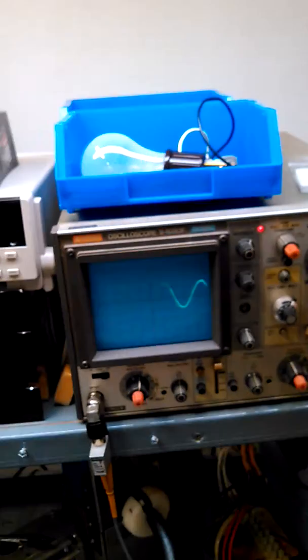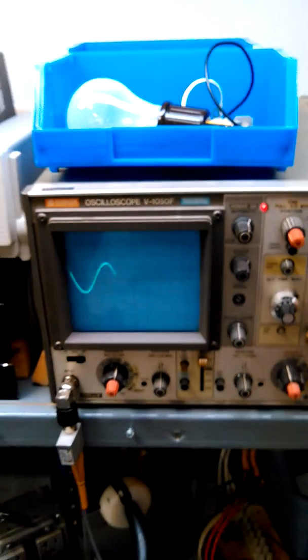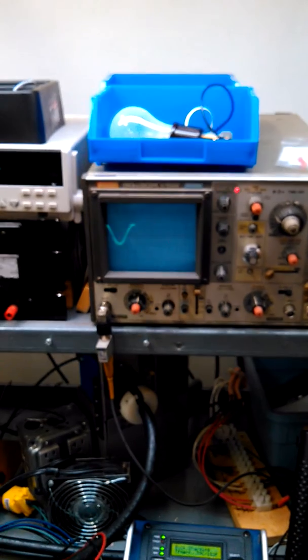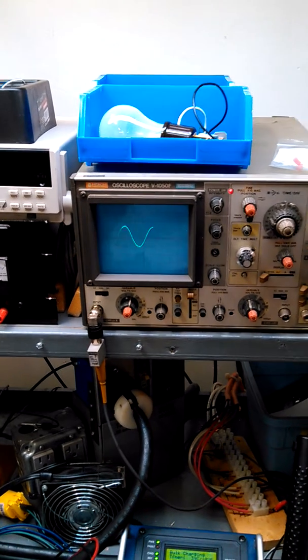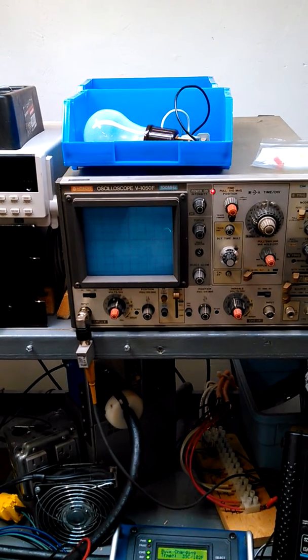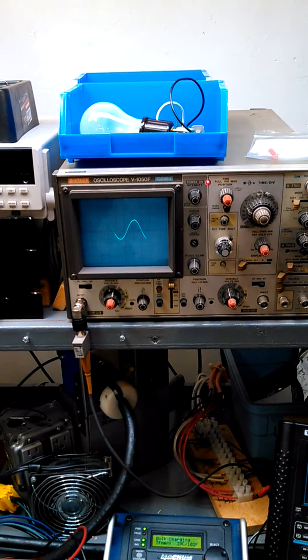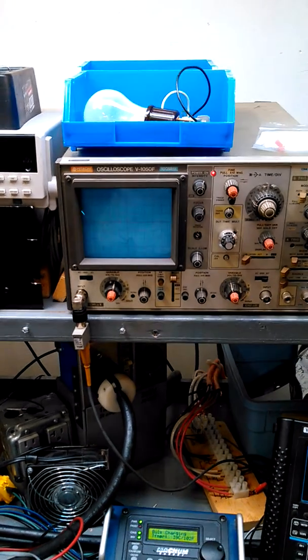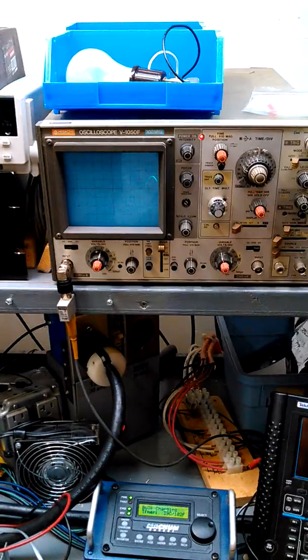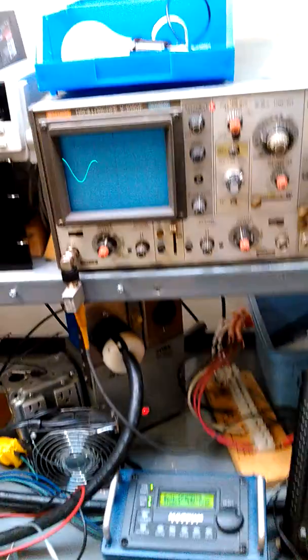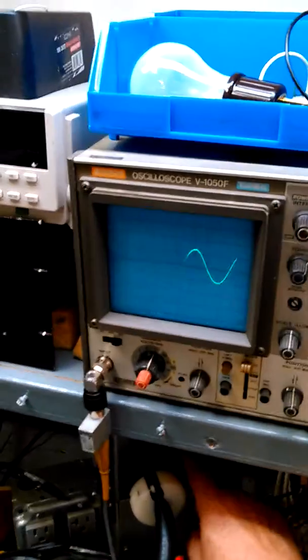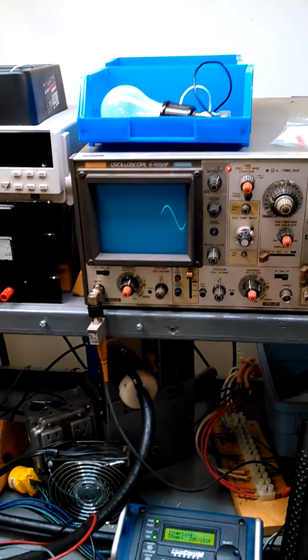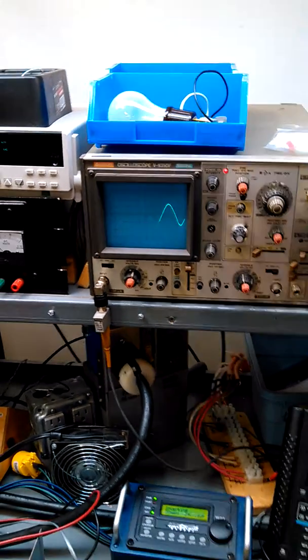Right now in the charge cycle, the sine wave you see on the scope. I'm not sure the camera's synchronizing with that very well. It's an old analog scope, so there's a lot of blinking when it's putting on a 60 cycle sine wave, but it's good enough for monitoring. If I turn off the AC power, it immediately flips to the inverter sine wave. So that's the output from the inverter.